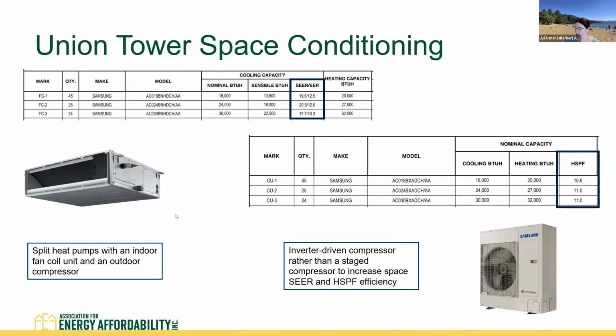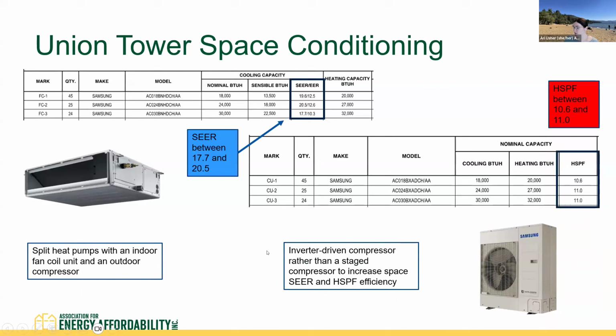And we've got pretty high efficiency ratings here. We've got a SEER between 17.7 and 20.5. And then we've got HSPF, which is the heating efficiency, between 10.6 and 11. And these are a good amount above the mandatory minimum efficiencies. And that's really going to be driven by an inverter or variable speed compressor. So it's always important to consider an inverter-driven, variable speed compressor, rather than a traditional staged compressor for your heat pump. And that's really going to be the driver of efficiency in terms of this equipment.